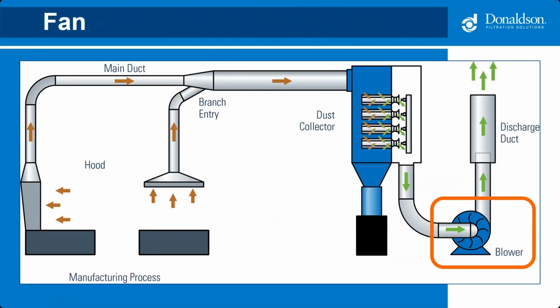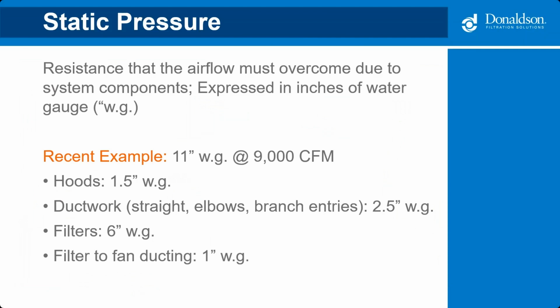So we'll talk a little bit about the fan now. When designing a system, the very last thing we do after completing all the airflow calculations is select and size the fan. A critical component of fan design is static pressure. It's basically the resistance that the airflow must overcome due to system components. It's expressed in inches of water gauge. When we design a system, we calculate the total system static pressure so that we can size that fan properly.